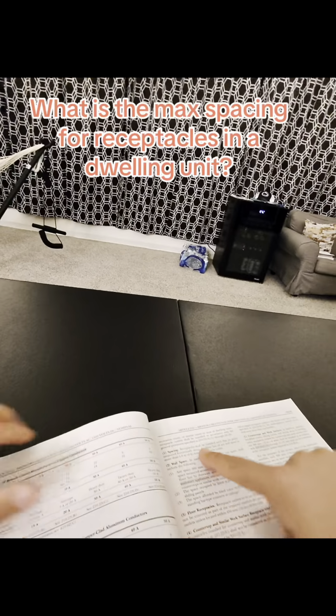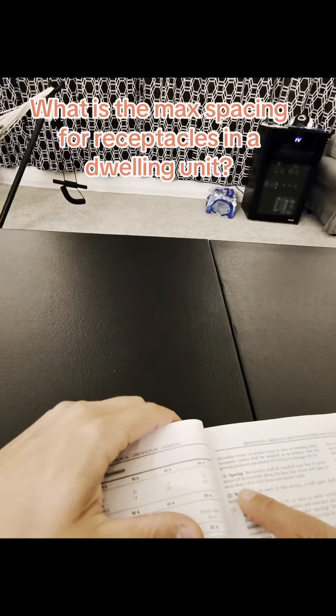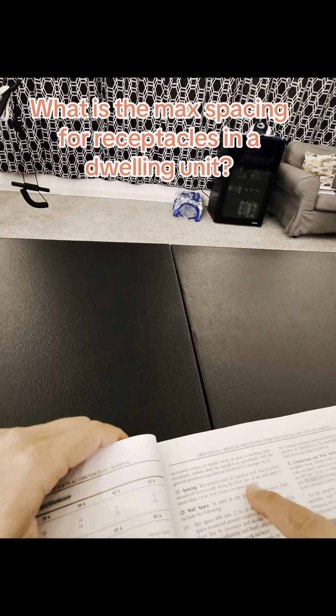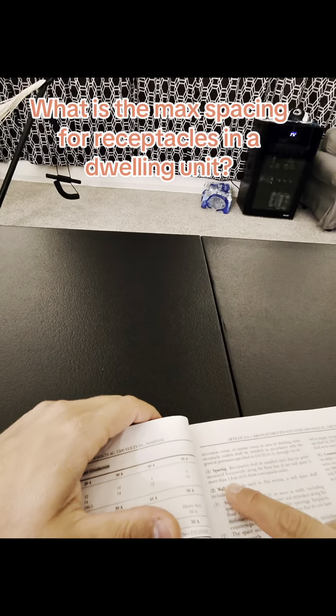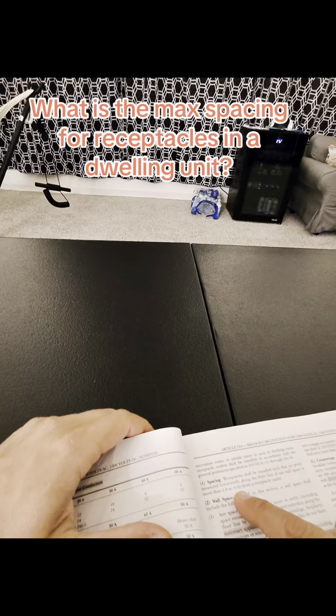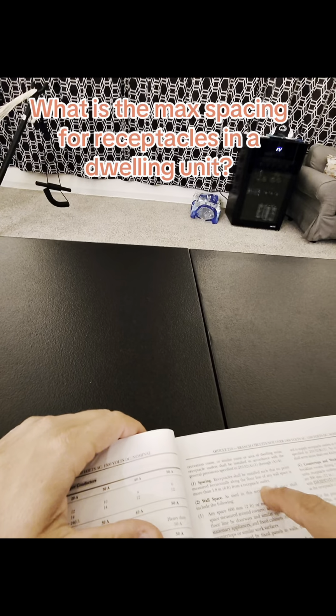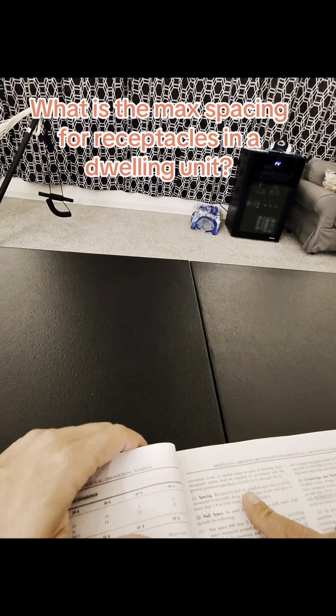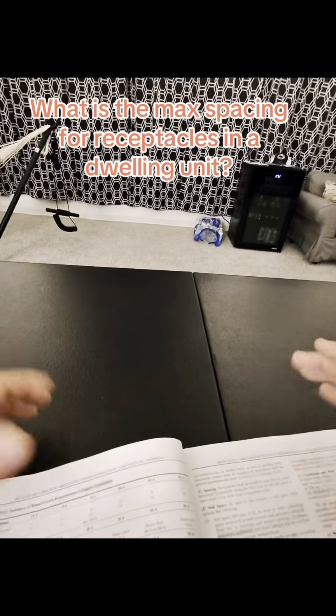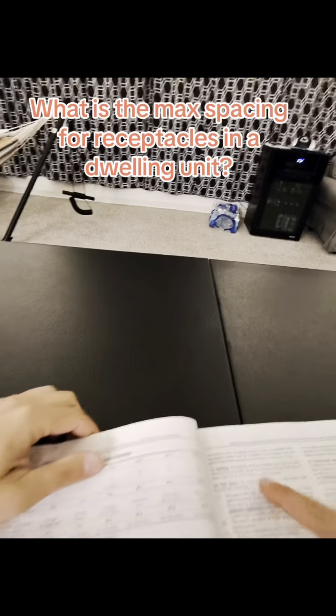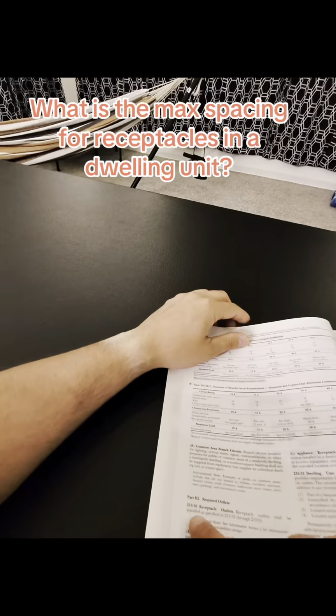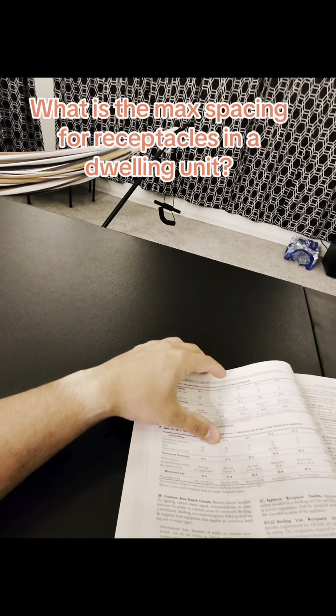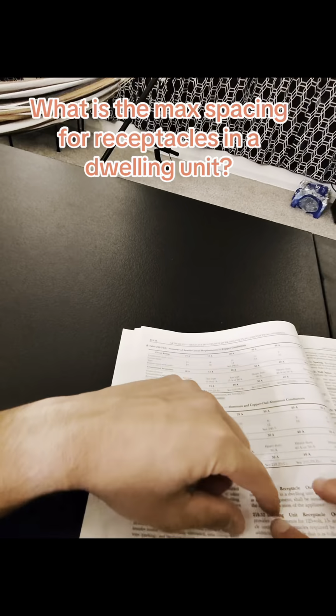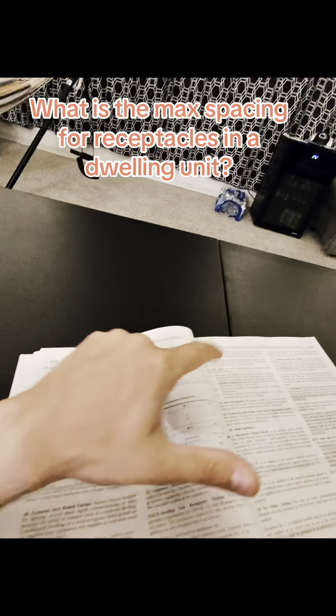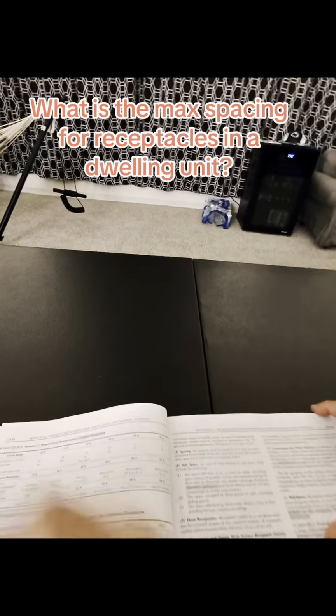Spacing. Receptacles shall be installed such that no point measured horizontally along the floor line of any wall space is more than 1.8 meters or 6 feet from a receptacle outlet. That is exactly what we're looking for. So, the answer to the question is no more than 6 feet. That was found in Article 210, but in specific, it was found in 210.52(A)(1). That is the answer to the question.